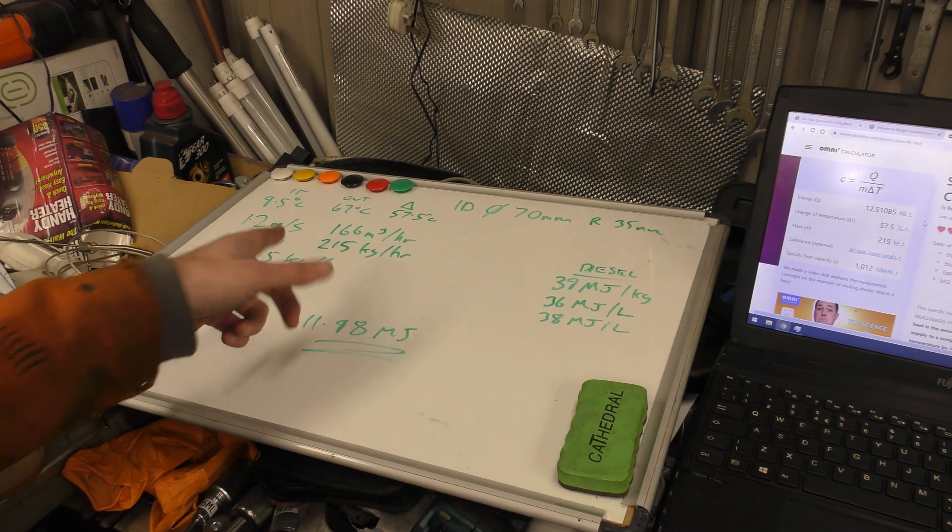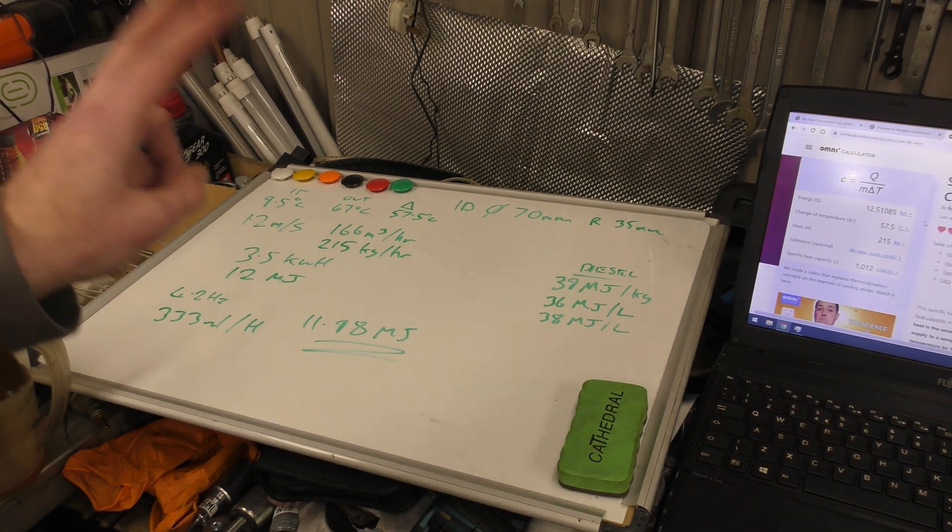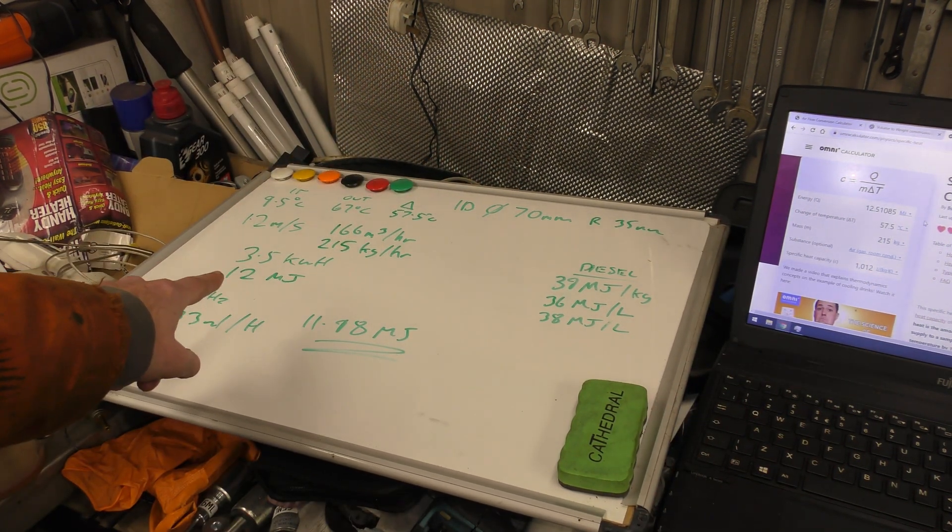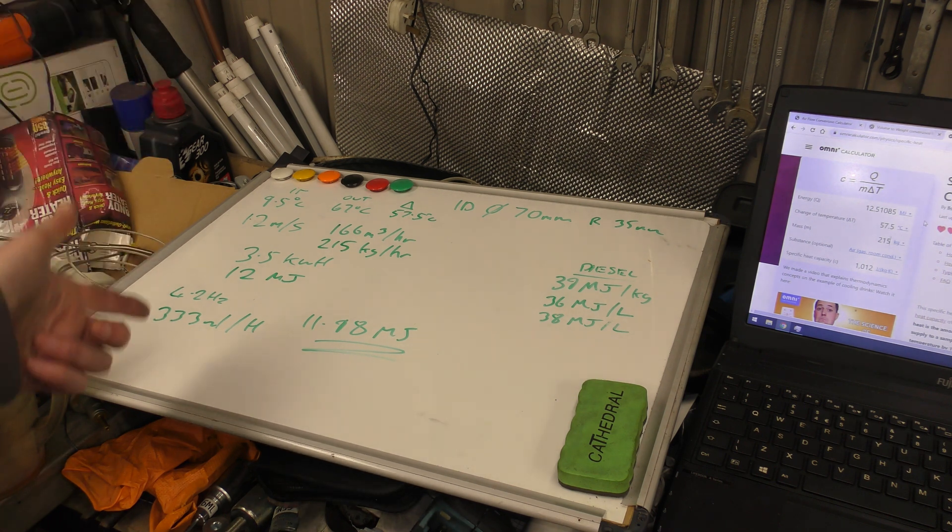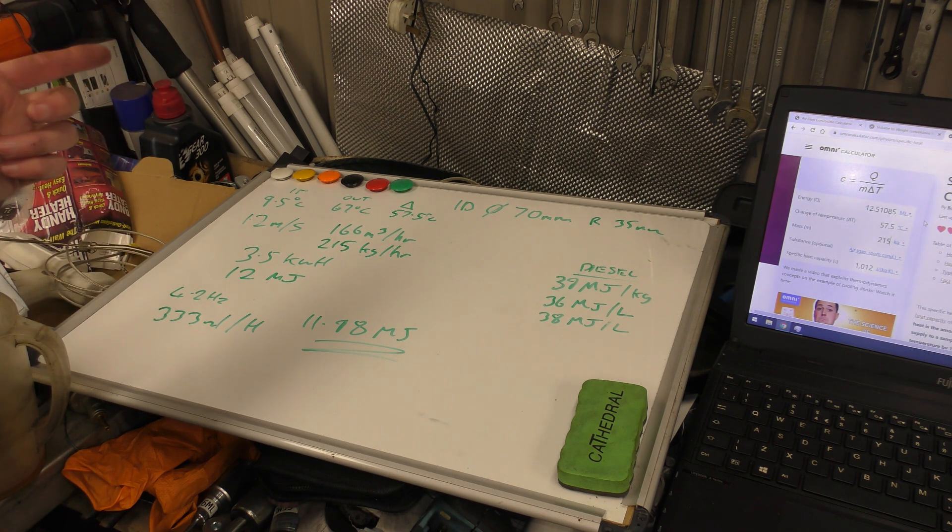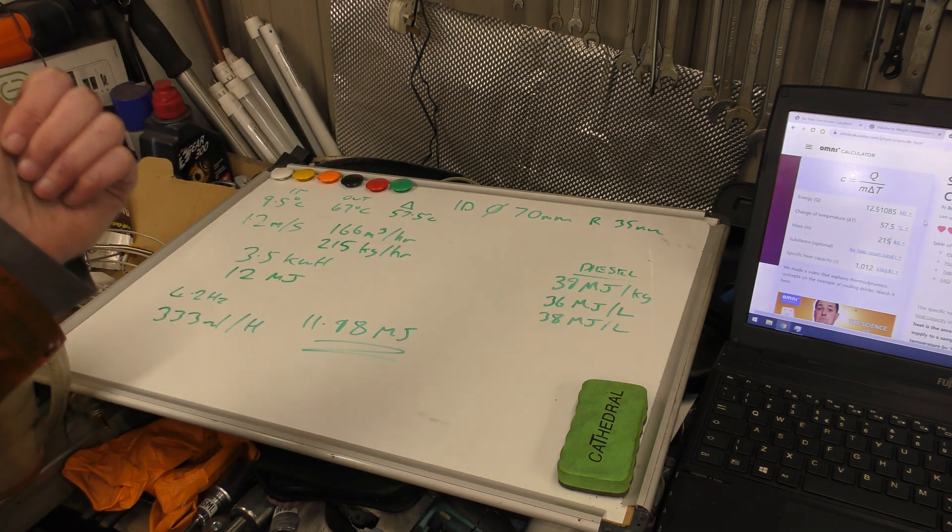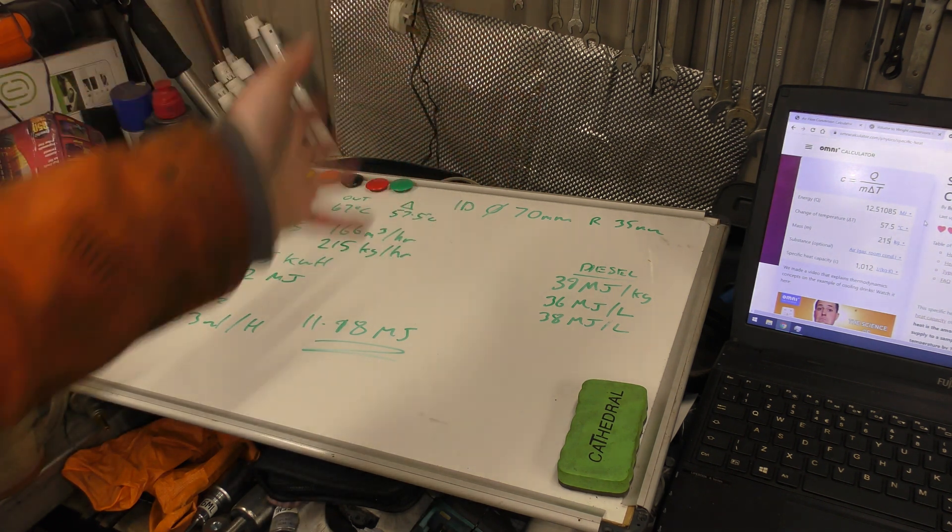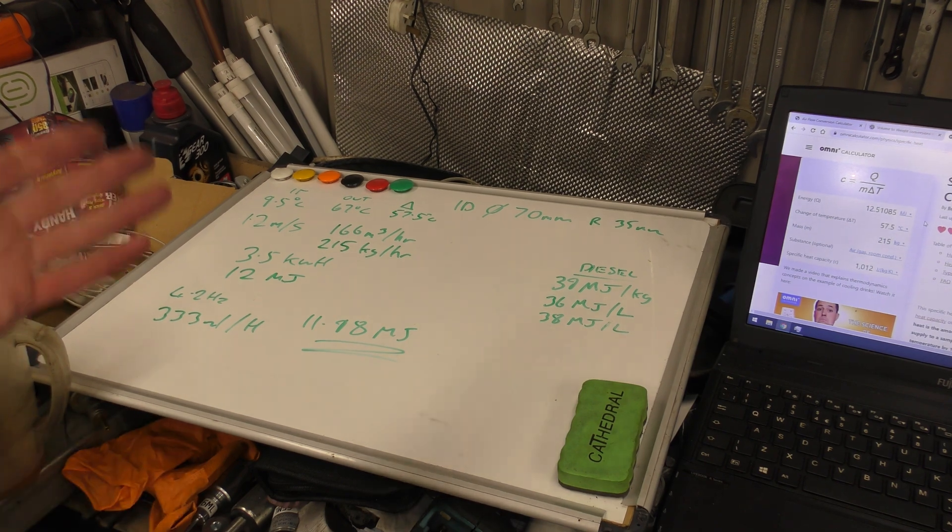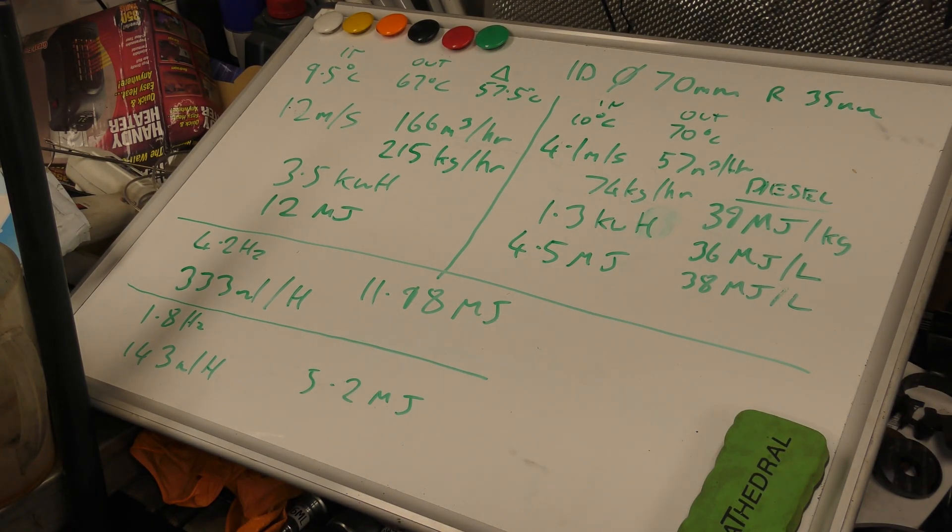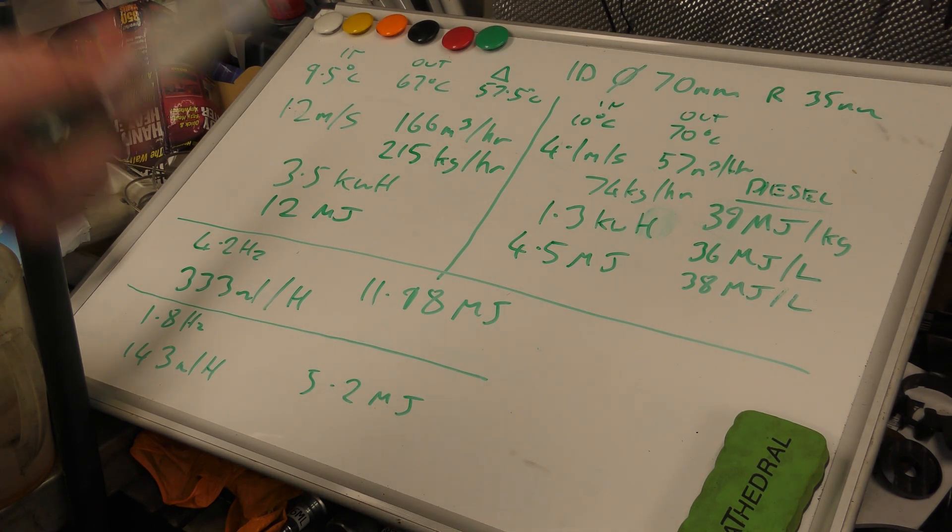But it gives us a ballpark. For the 4 kilowatt heater we're getting 3.5 kilowatts of heated air output at 6.2 hertz. I will go now and run on low and do the same and write down and I will come back and show you the low numbers. The rain is now battering off the workshop roof. Good old Scotland.